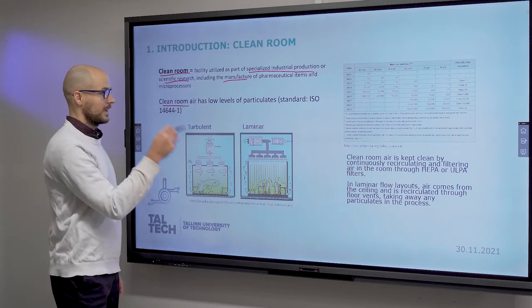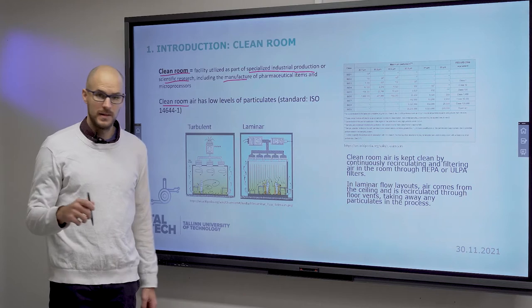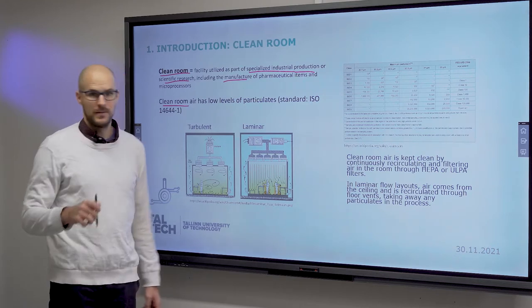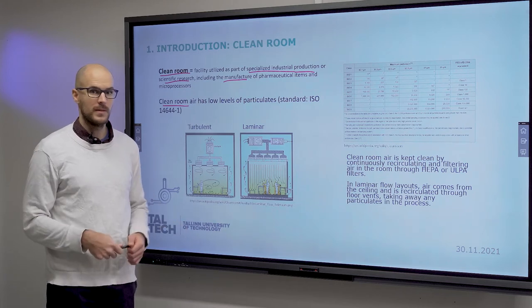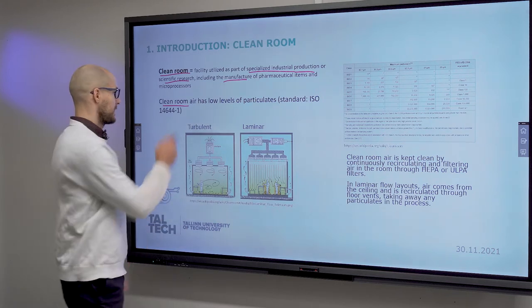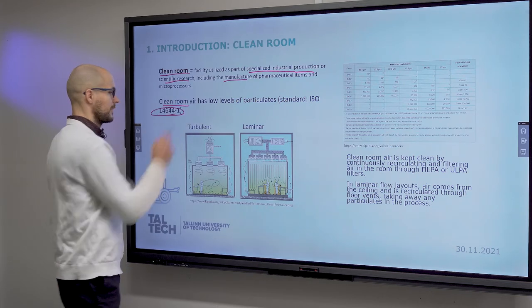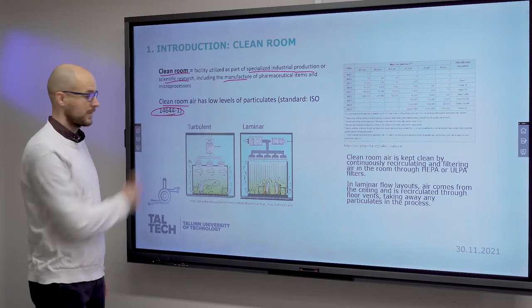Clean room air has low levels of particulates because dust can really negatively interfere with the production processes that we will discuss in the next video. And the standard that determines the level of allowed particulates is this ISO standard.